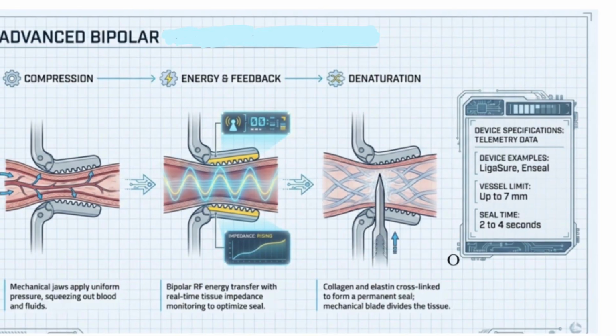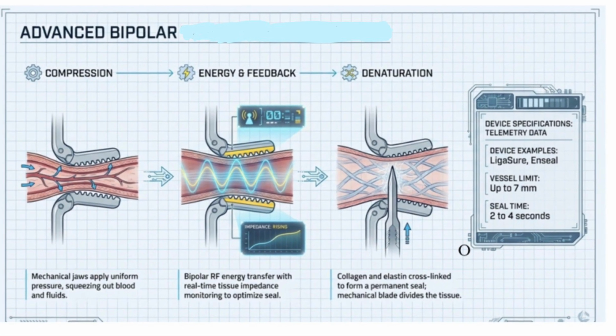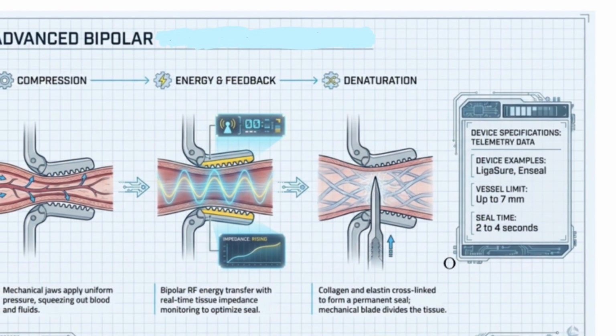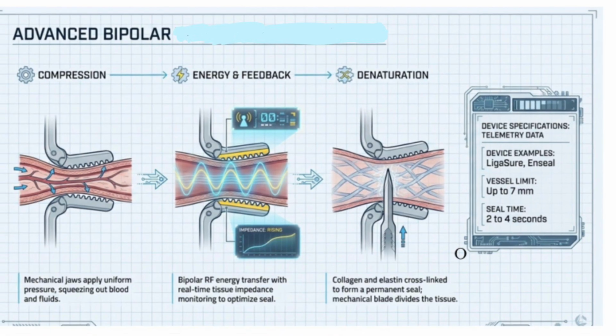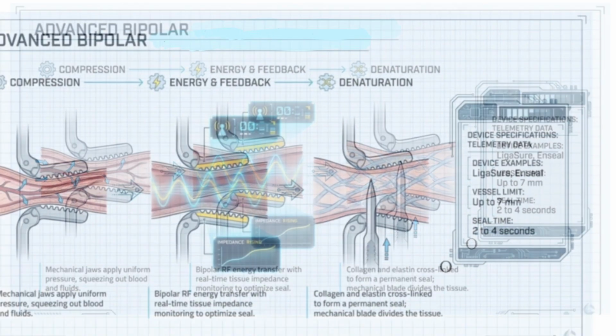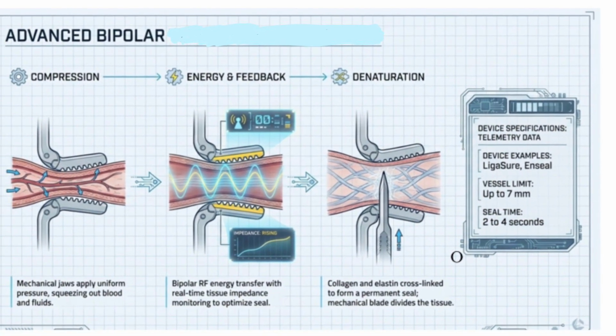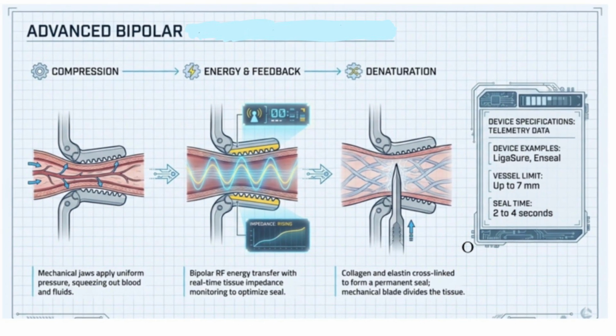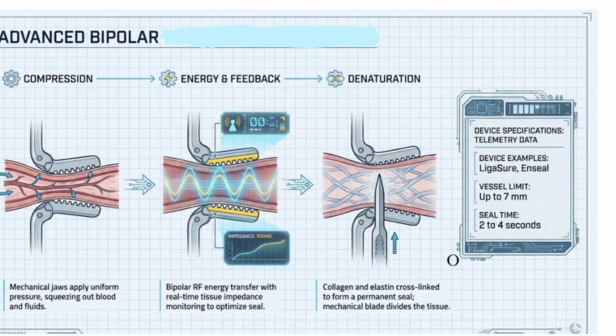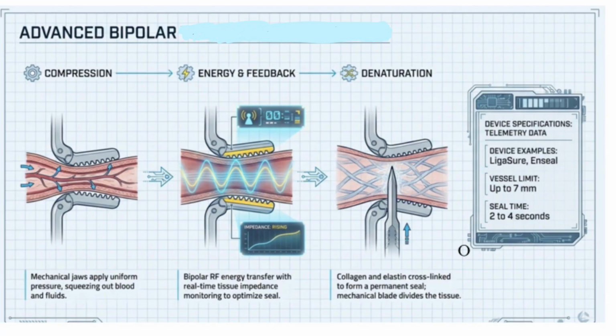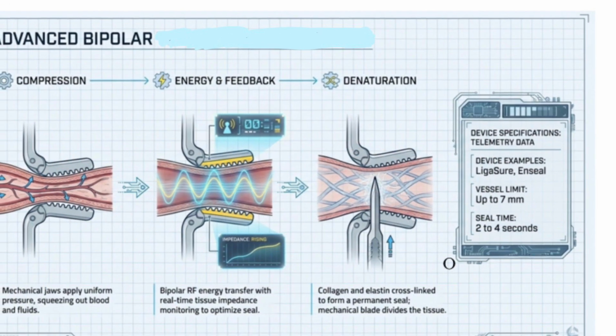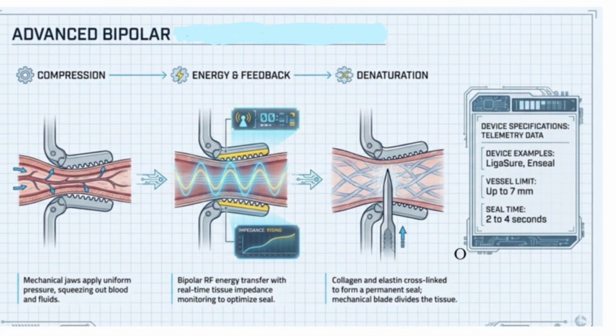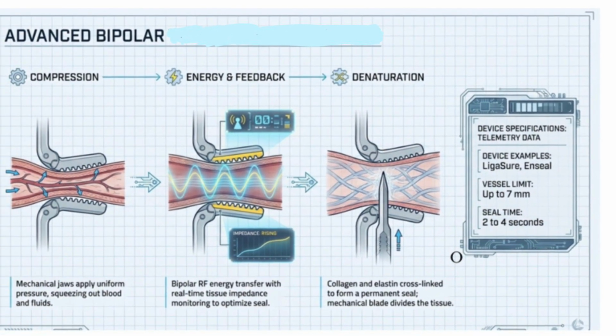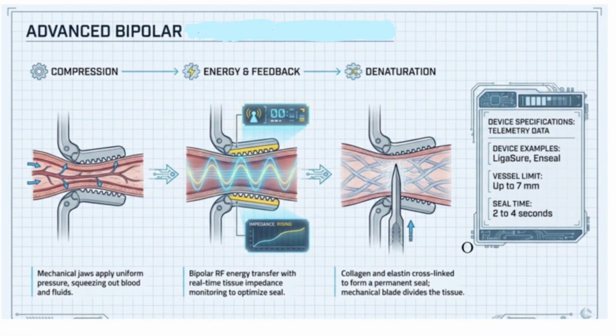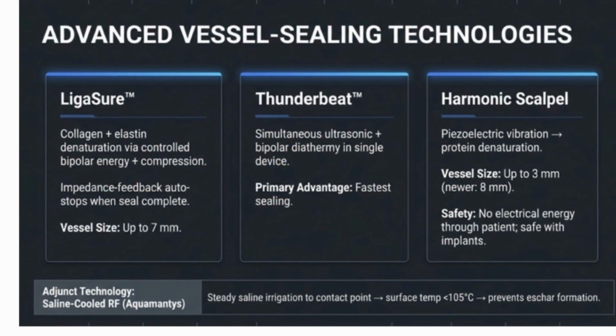There is compression. The mechanical jaws are applied uniformly, and uniform pressure squeezing out blood and fluids is produced. Then the energy is given. The bipolar radio frequency energy transfers with real-time tissue impedance monitoring to optimize the seal. Then denaturation. The collagen and elastin are cross-linked to form the permanent seal, and a mechanical blade is used to divide the tissues.